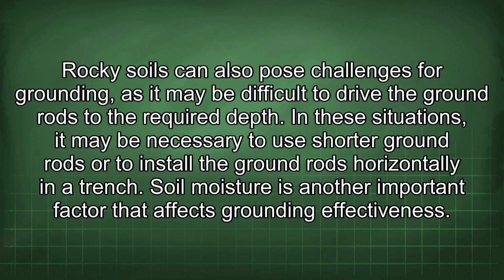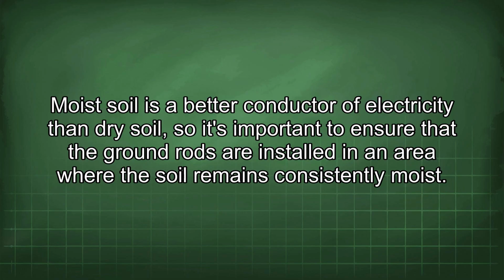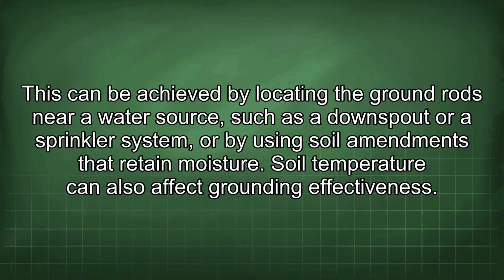Soil moisture is another important factor that affects grounding effectiveness. Moist soil is a better conductor of electricity than dry soil, so it's important to ensure that the ground rods are installed in an area where the soil remains consistently moist. This can be achieved by locating the ground rods near a water source, such as a downspout or a sprinkler system, or by using soil amendments that retain moisture.